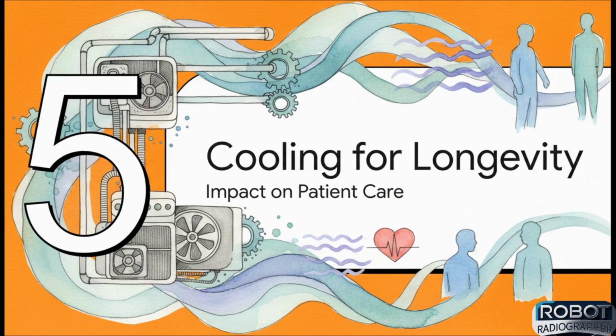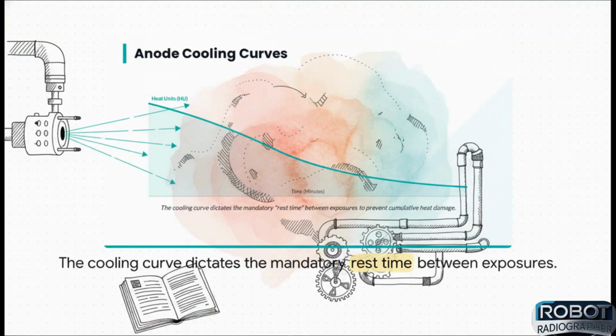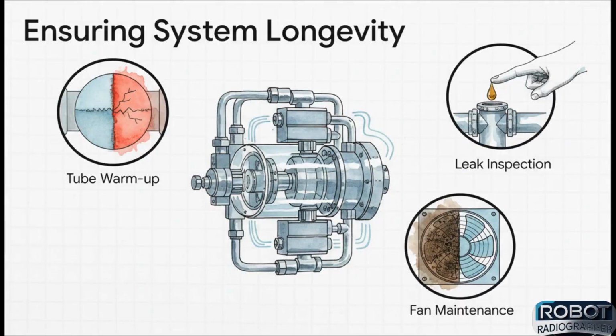This right here, this is the operator's rulebook. It's the anode cooling curve. It shows exactly how many heat units have built up in the system and precisely how long it's going to take for them to go away. And following this curve is absolutely mandatory. It tells the radiographer exactly how long they need to wait between scans to prevent that heat from building up and causing permanent damage.